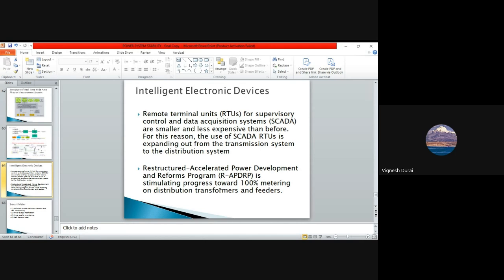Intelligent electronic devices and remote terminal units, RTUs, are used for supervisory data. SCADAs are similar, smaller, and less expensive than before. Because of this lower cost, we are using SCADA RTUs, and it is expanding from the transmission system to the distribution system. So, okay.